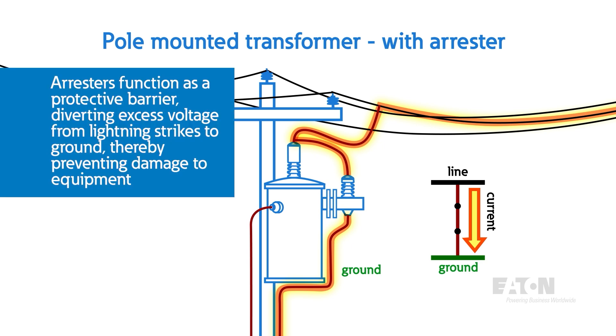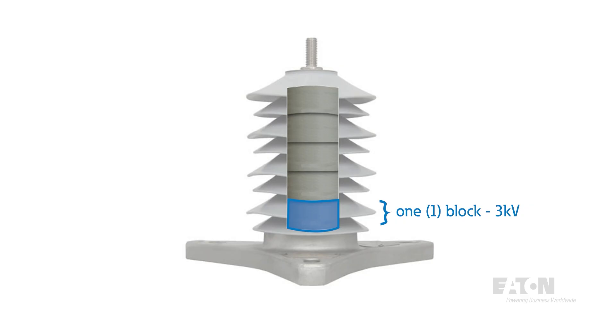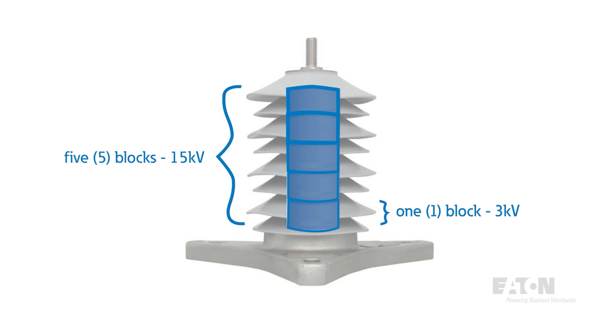Thus, arrestors act like a trapdoor, preventing the lightning strike from damaging equipment by shunting excess energy to ground. MOVs can be found in every surge protection device, like the ones in your home. But since utilities are working with voltages typically above 7,000 volts, the MOVs used in arrestors are much larger. Each block is usually designed to be around 3 kV and then they stack together to form higher voltage ratings.